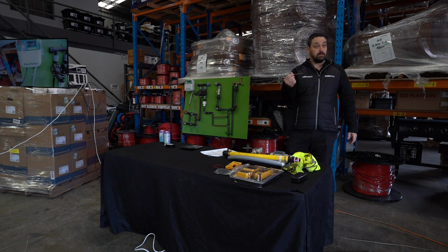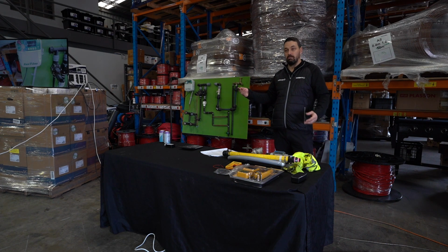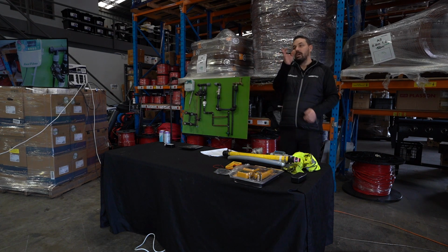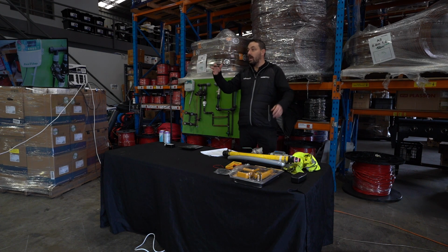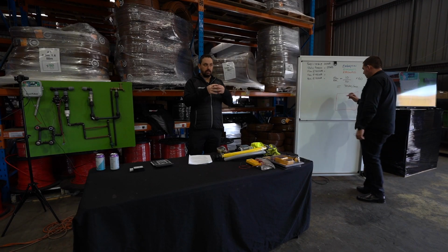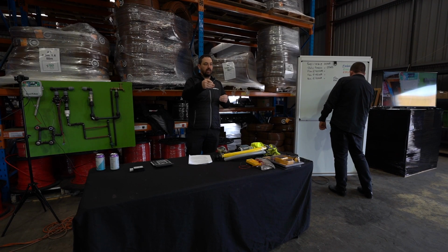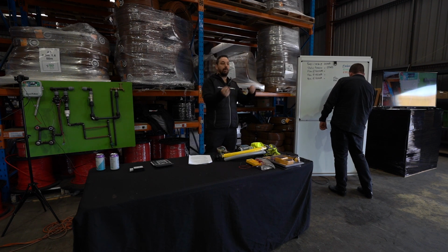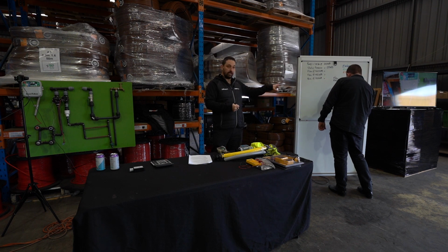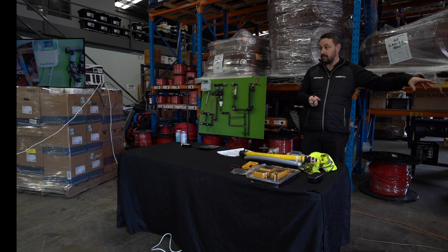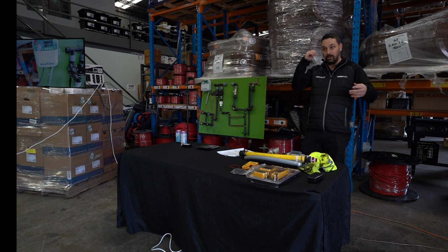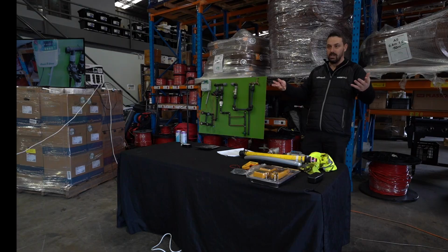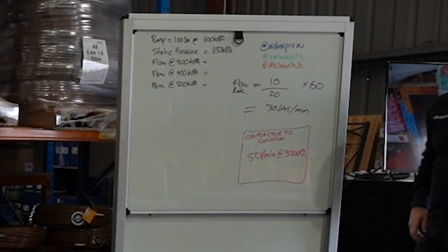What you will see on not just our designs, but most irrigation designs out there, is that it will say this system's designed as 50 litres a minute at 350 kPa. We do that to make sure that a $50,000, $60,000, $200,000 job doesn't go in the ground and then we realise it doesn't work. So we're trying to capture that information prior, because if there need to be changes, we can do that before the construction phase. And as you guys know, you don't want to hand over to council an asset that doesn't even deliver the turf quality that you want.